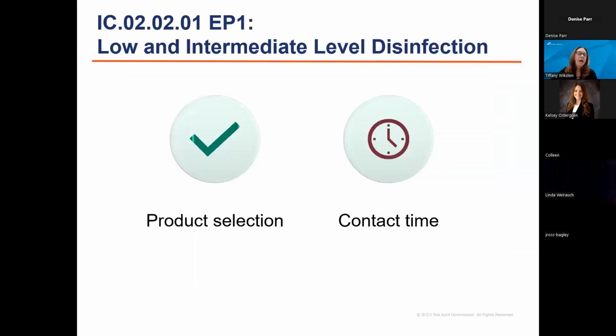When we talk about IC.02.02.01 EP1, so low and intermediate level disinfection, there are two main concepts. One is product selection, and the other is contact time. You have to make sure that you're selecting a product that is approved for use by the manufacturer of the item that you're disinfecting. Glucometers are a really popular one.